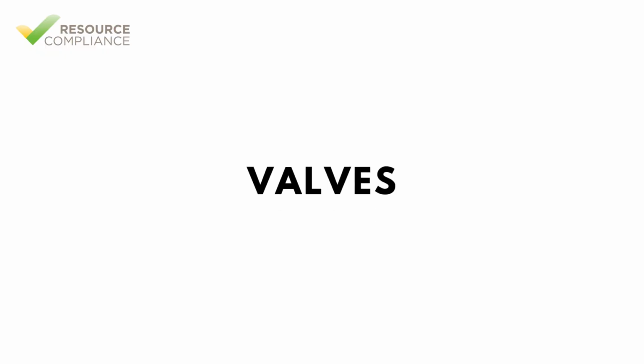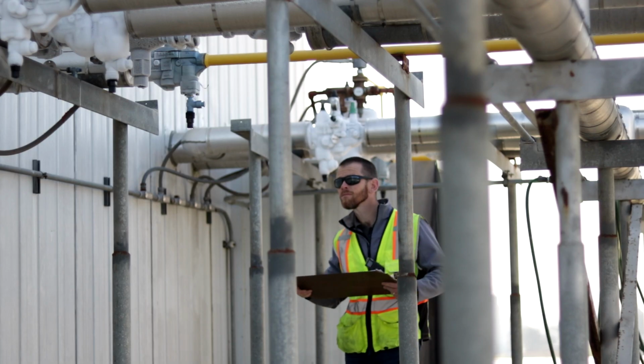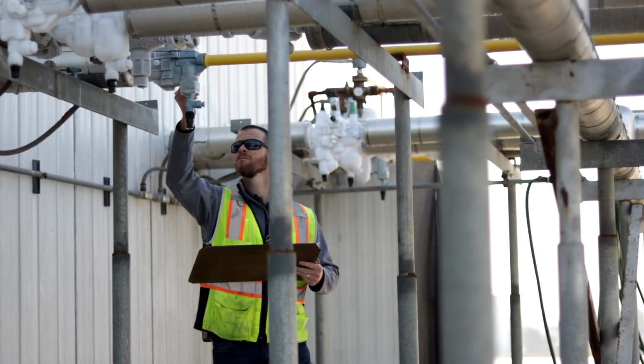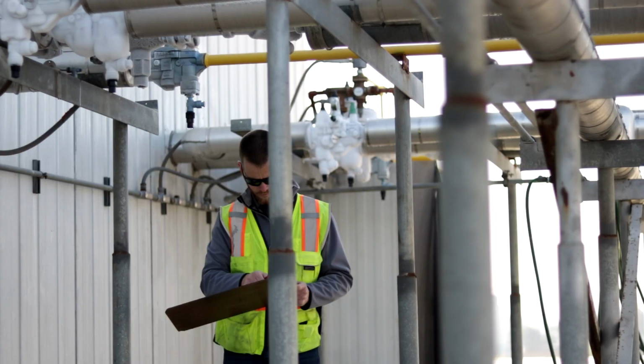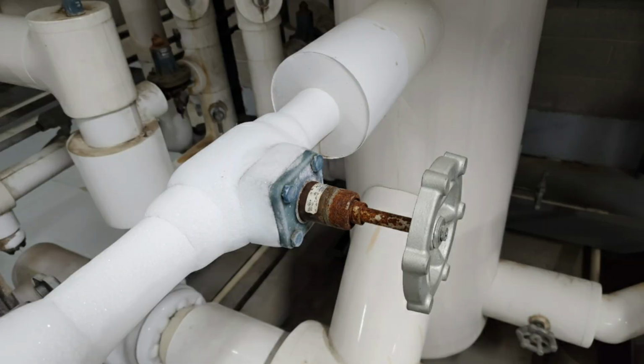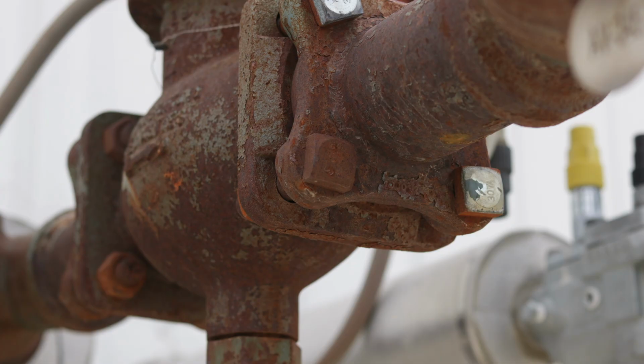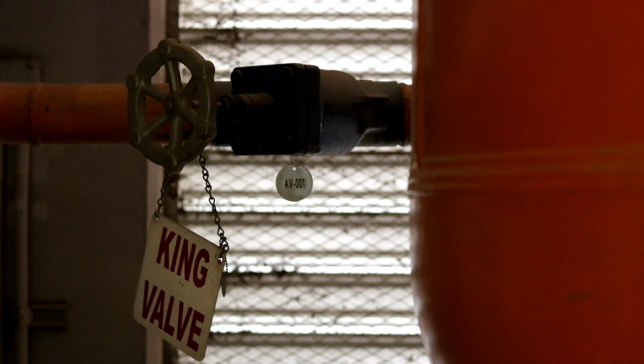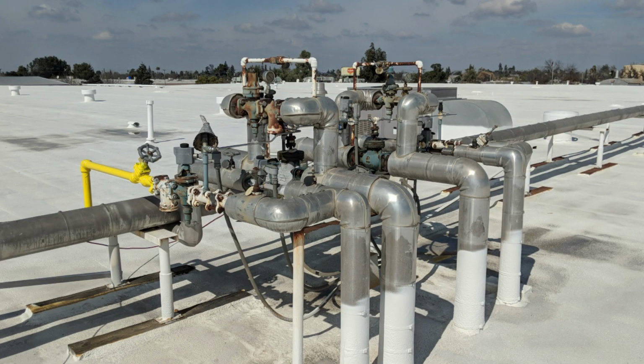Valves are typically inspected with the refrigerant piping. In addition to verifying the standard items such as surface corrosion, valve inspections must look for corrosion or paint on the valve stem and loose bolts on flanged connections. Valve maintenance must not be overlooked. Annually, emergency shutoff valves must be exercised and lubricated. Other valves require the same maintenance, but on a 5-year frequency.